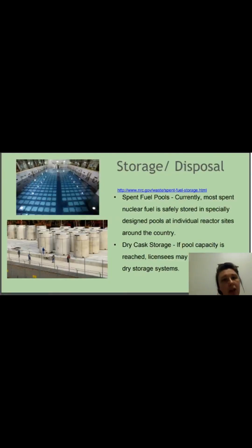So once I pull out a fuel rod, if I'm not going to recycle it, the next stage I need to do is to cool it off. And this is a process called the spent fuel rod cooling. And this is where I put them in water. Now, water is a great barricade. It allows it to do a couple of more chain reactions as it needs to, but not enough to make power, so it can't boil the water, but it keeps the radiation within the water itself. And so I will put it into a storage pool, which will then hold individual reactor cores for a number of years, between 5 and 7 years. And then after 5 to 7 years, I will put it in what's called dry cask storage.